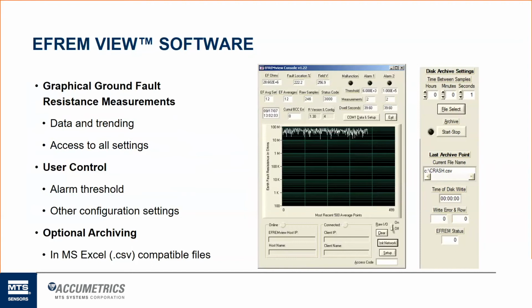So the user can then adjust some of the thresholds down in the bottom right corner. There's an access code, and this is detailed in the manual that every system would get. The access code is the same for every EFREM system. Then that will allow you to go into the setup and change those field resistance threshold values. Some users like to keep those a little closer together, so instead of 100K and 2K, they may opt for something like 60K and 20K. Again, that's totally customizable to each plant and how they choose to interface to that output.